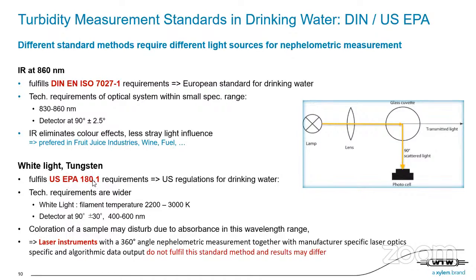White light tungsten, whereas US EPA requirements, they have a white light with a color temperature of the lamp from 2,200 to 3,000 K, and the detector is with a wider angle and must detect between 400 to 600 nanometers. So in drinking water, it's less of a problem, but coloration of a sample, for example, in fruit juices, may disturb and bring other values. And by the way, this means that, for example, if you are measuring fruit juices, you will have a different value between IR and white light, which for a quality proof is not important if your company-specific standard operation is just giving you the value you need. On the other side, the fruit juice industry usually uses IR, particularly because of these color effects.